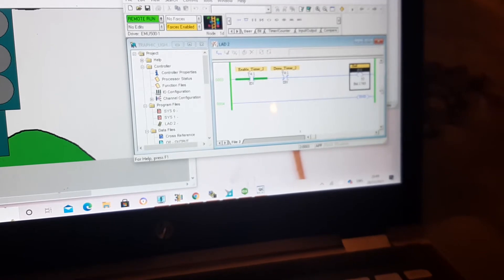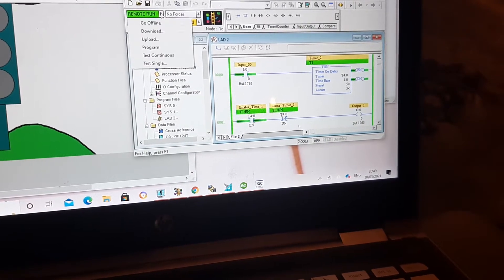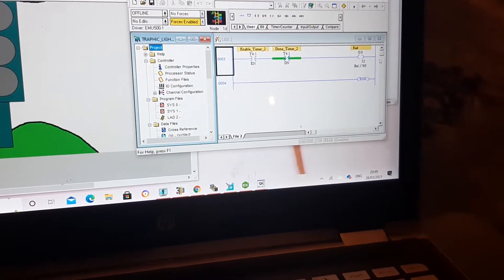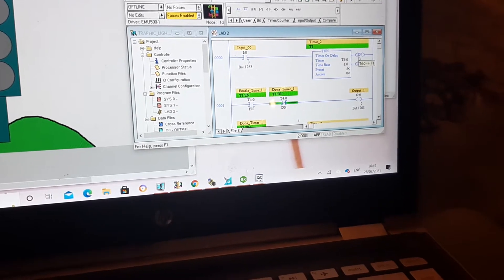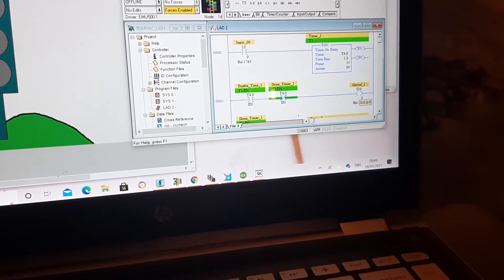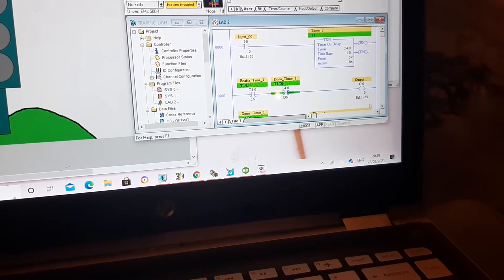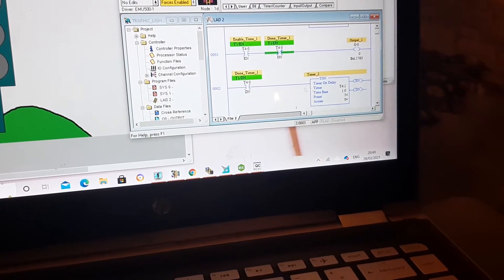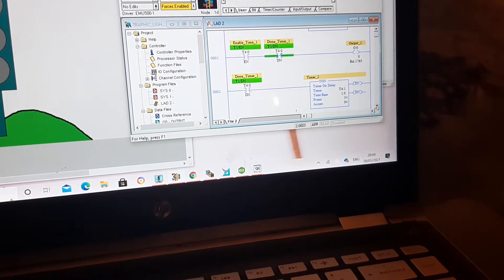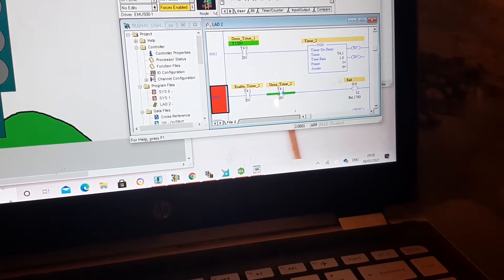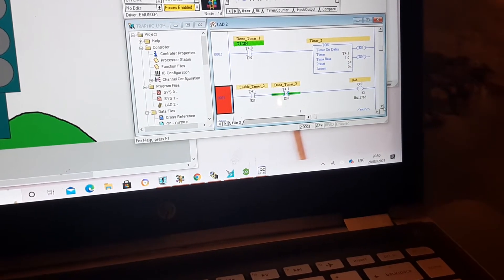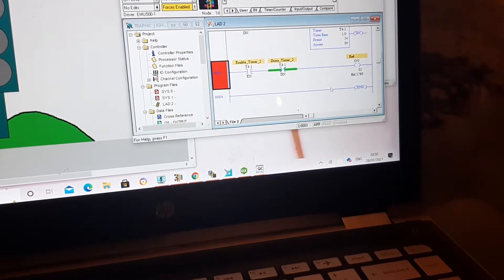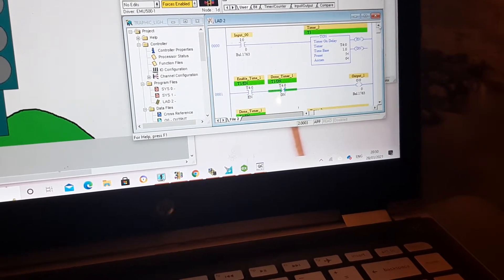So here, if I show what we have, it's very simple. Let's go to offline. I'm just turning things on with the switch. I have my first timer and then the enable and the done pin are connected to each other this way, and they are going to turn on my light. This is, if I'm not mistaken, my green light. And then the done pin is turning on my second timer. These parts are easy for you because you have done it last semester. So done pin and enable pin are connected to each other and they are turning on my red light. And that's it. So I don't have a loop, it's happening only once, but if I keep turning it on and off the whole system because of the switch, you will see that on Graphworx.